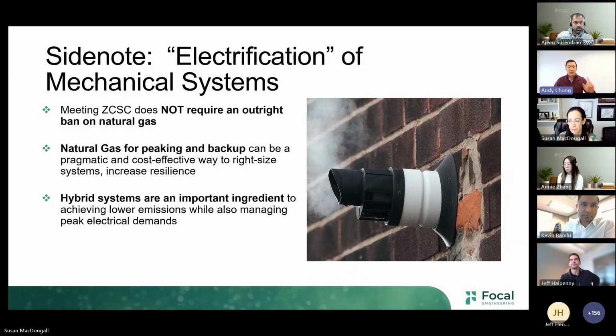Yeah, definitely - what you mean is if we went for an electric resistance boiler instead, that has huge hydro implications because it switches on the coldest day of the year and takes over all the load from the heat pump. The gas boiler does not do that. So in buildings where I already have gas for a fireplace in the residential area, or a CRU with a coffee shop or commercial kitchen, if I've already got gas service to the lot and can put a small meter on there, it's really not a big deal to use that gas boiler again for that peaking role. Thank you, Jeff, for chiming in, because the objective is to make it easier on our electrical friends and on the utility.